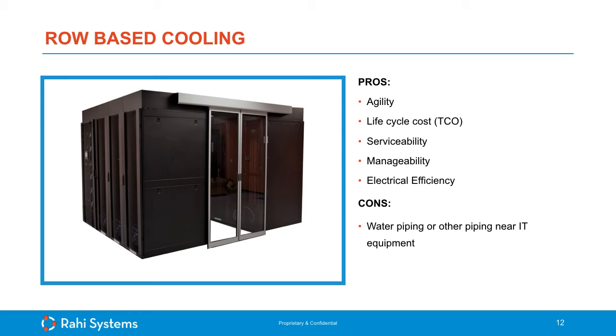But as compared to room-based cooling, the IRC has a better ability and probably a better agility to handle the variable density heat loads. Like CRACs and CRAHs, also in custom air handlers, one of the advantages is it is a standalone unit. Even though it sits in a row or a pod next to the IT loads, it's much easier to manage and service as compared to obviously the liquid cooling and the rear door cooling systems.